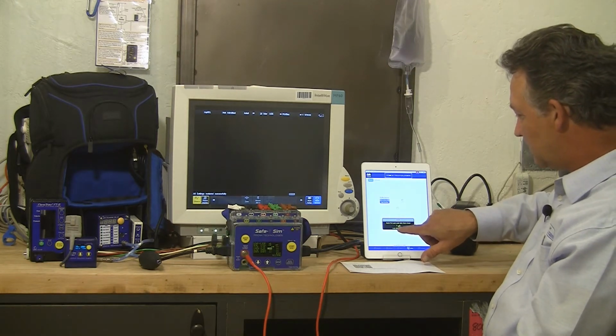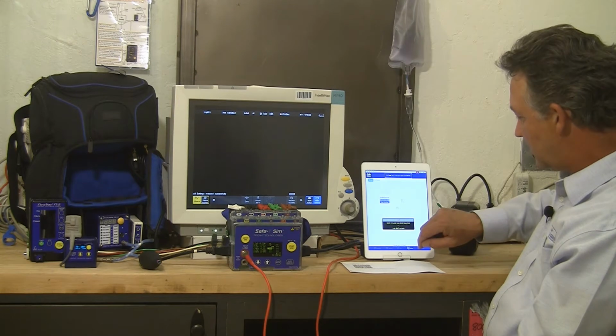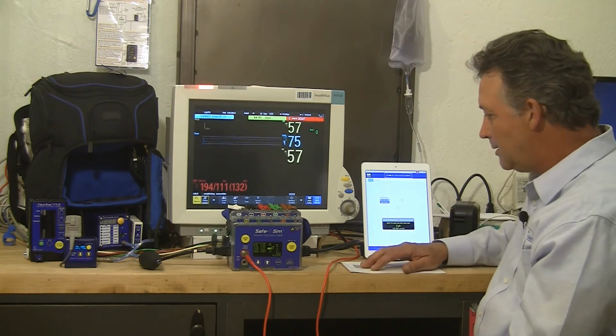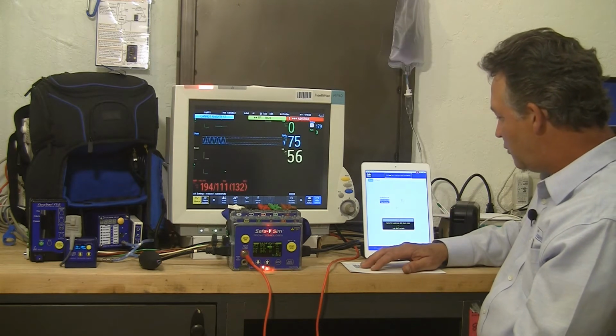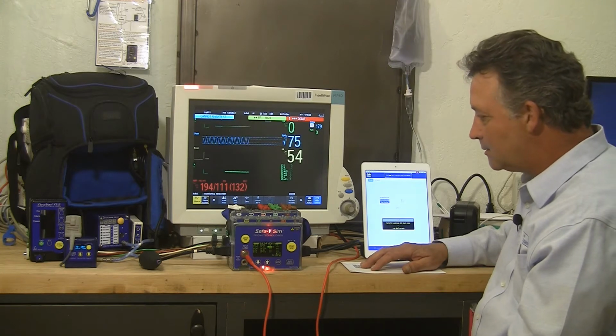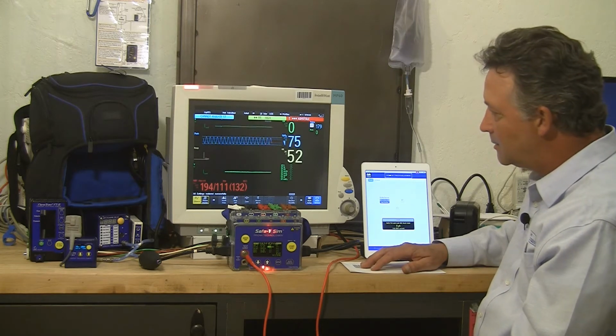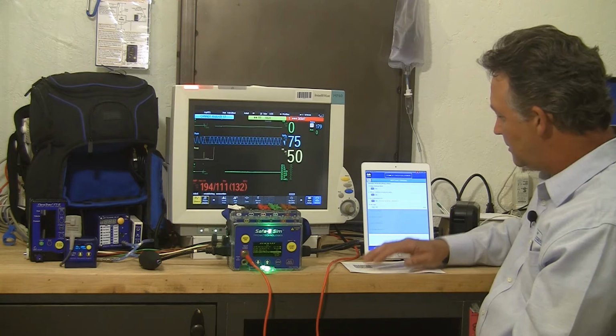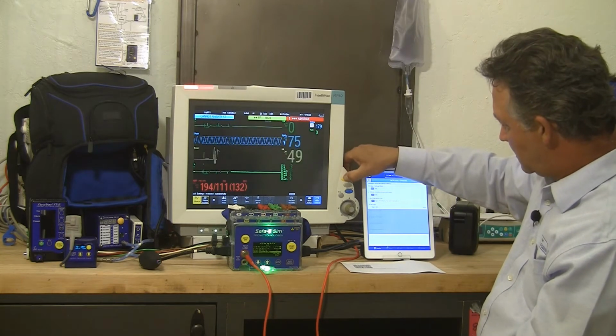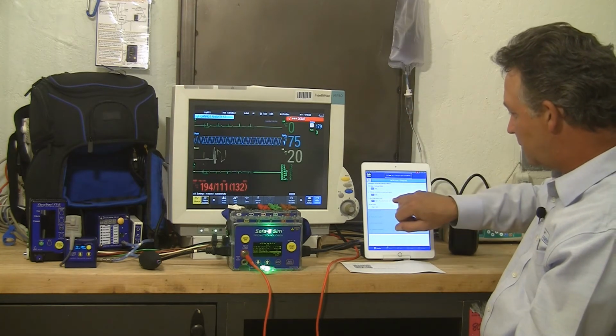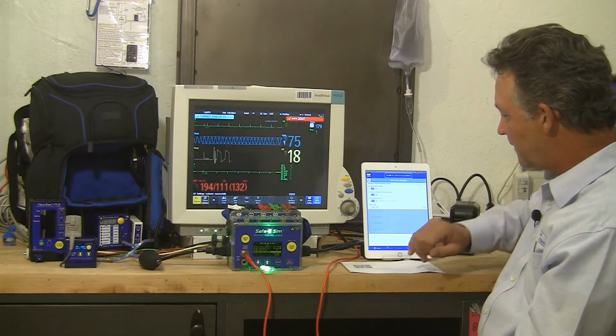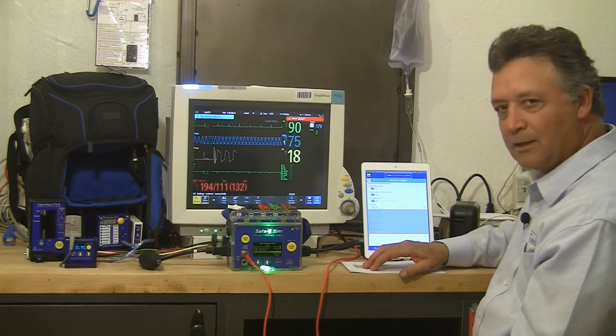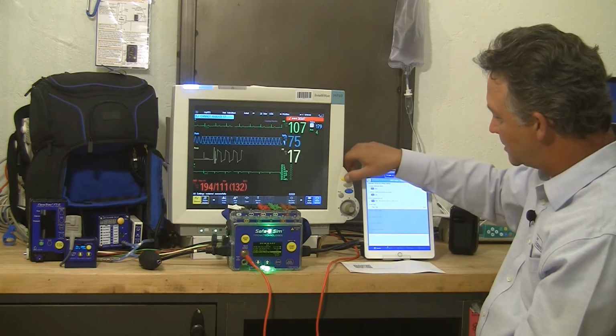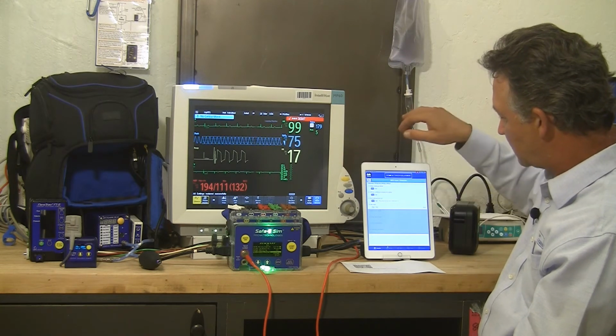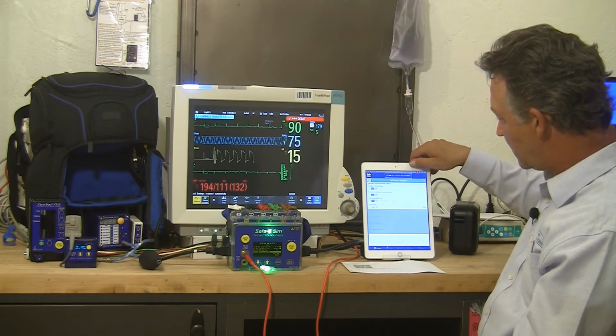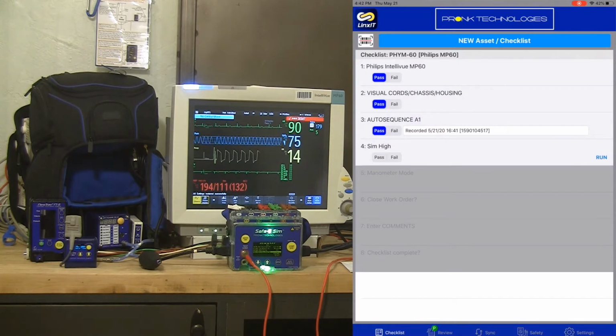So I can see it's into its normal polarity lead leakage test. Now it's doing a lead leakage ground test, and it's moving on to its applied parts test or ISO test on the ECG leads, and it's done. It finished that auto sequence electrical safety test, and it found that the results were passing based on your predetermined limits, either by the hospital policy or the CMMS system configuration.